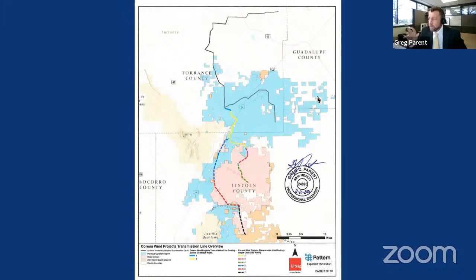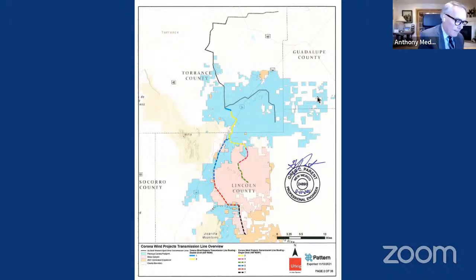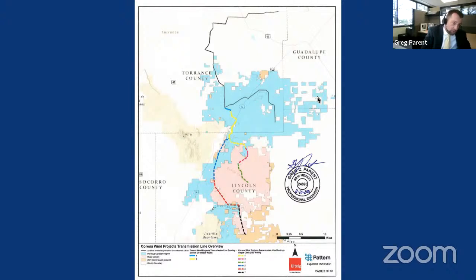One of the circuits would be taking approximately 1,200 megawatts. That circuit has the blue dashed line and continues all the way to the end of the blue, with no change in power throughout. That's 1,200 megawatts for one circuit. The other circuit picks up a substation at the point where the yellow turns to blue.